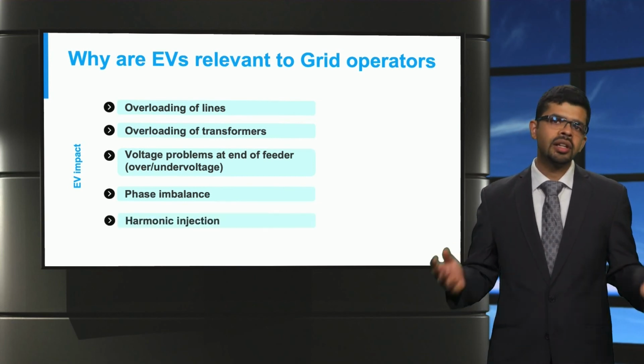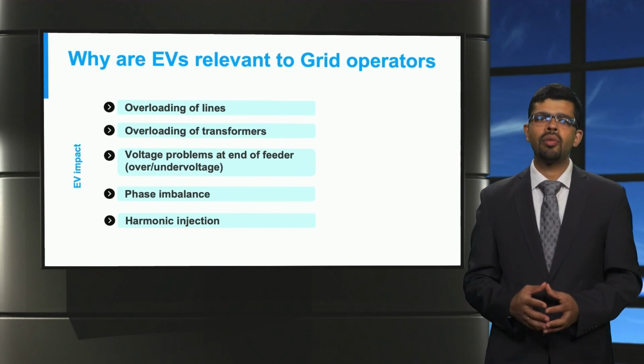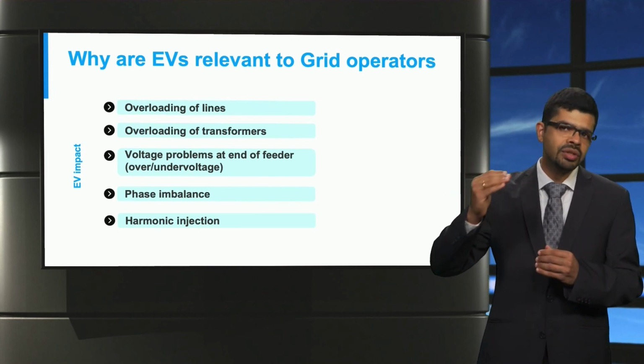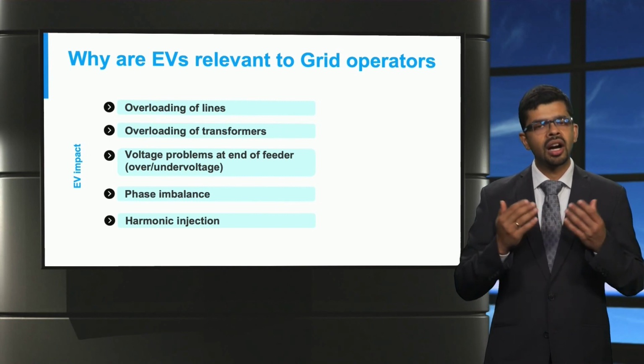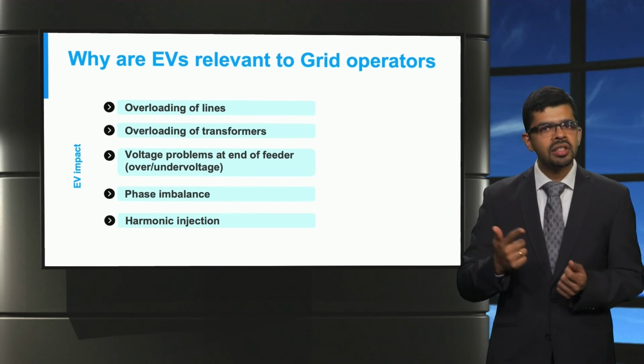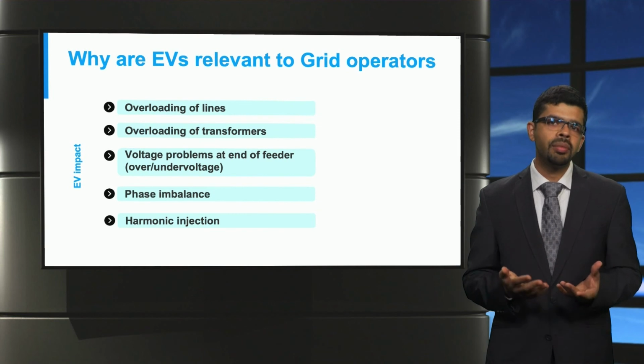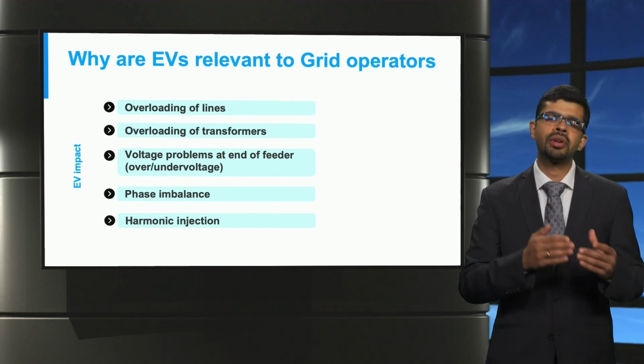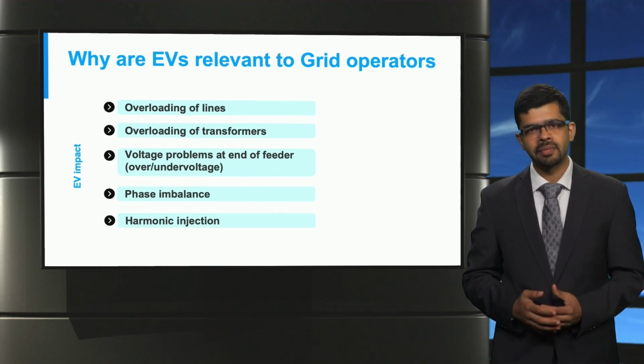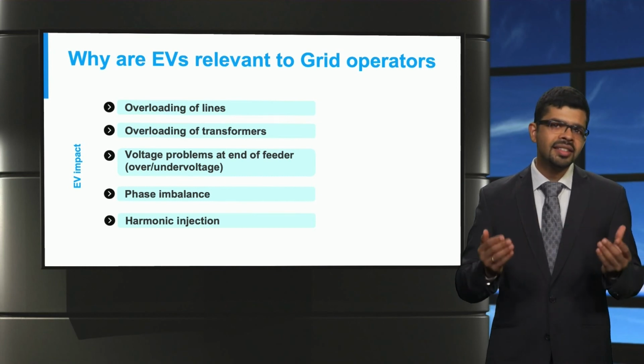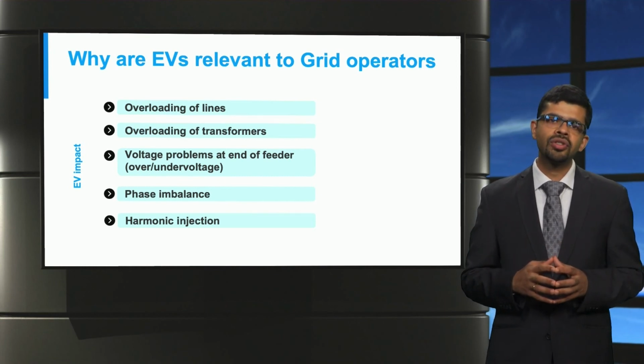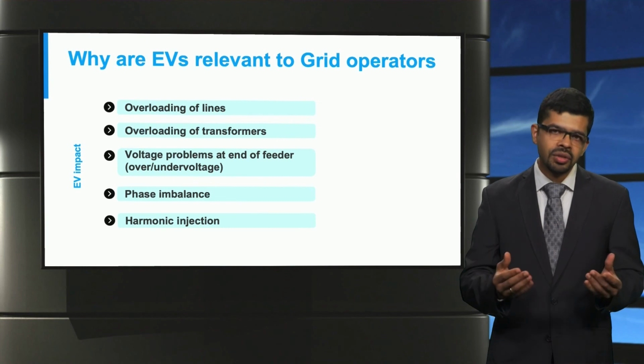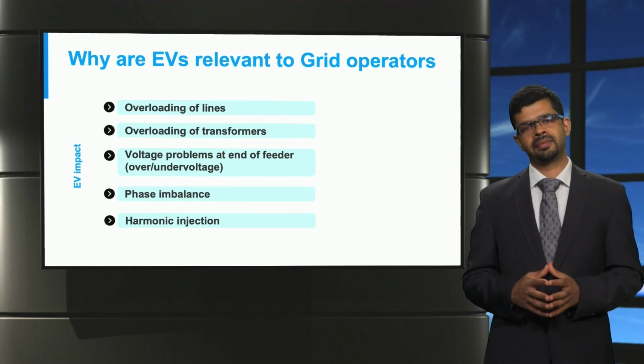Finally, since electric vehicle chargers are power electronic devices operating at high powers and high switching frequencies, they can inject harmonics, interharmonics and supraharmonics into the grid depending on the frequency of the harmonic with respect to the fundamental 50 Hz frequency. This can cause unnecessary resonance resulting in distortion of the voltage, flickering issues and heating of appliances.